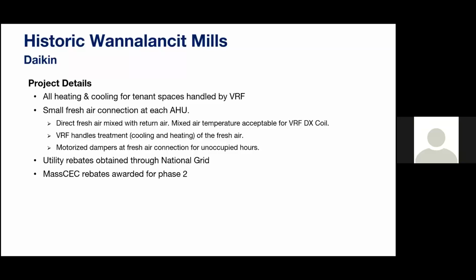So we have limits to the entering air temperatures on the coils to ensure we have adequate and comfortable leaving temperatures. With standard VRF indoor units, the coils are already sized for this, but in these more custom applications with semi-custom air handlers with VRF coils, we have to make sure that coil is sized for the correct capacity and correct temperature rise. And we also have motorized dampers tied to the fresh air ducts, so the air handlers are only pulling in that OA during occupied hours when there are occupants in the zone, as opposed to adding load to the coil when it's not necessary to handle that outdoor air.